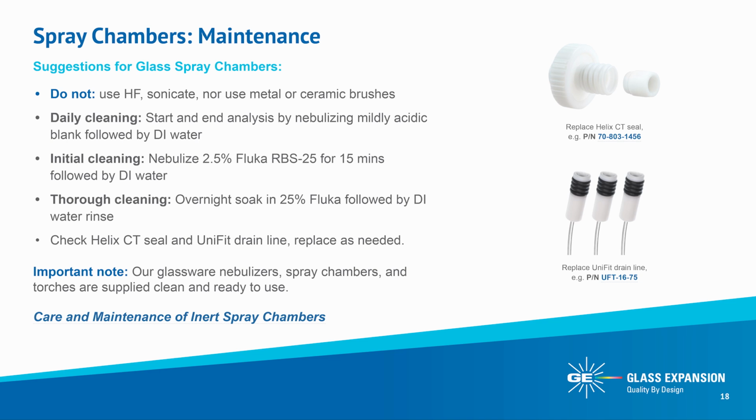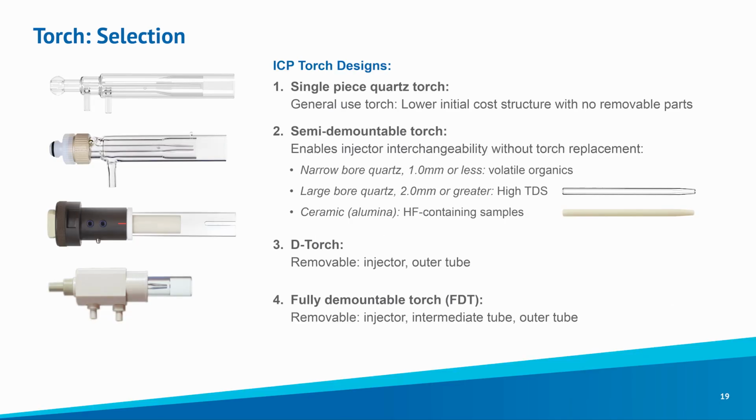Start by nebulizing a 2.5% Fluka solution for about 15 minutes, then follow with ultra-pure water. If that doesn't help, remove all fittings and soak the spray chamber overnight in a container with 25% Fluka solution.